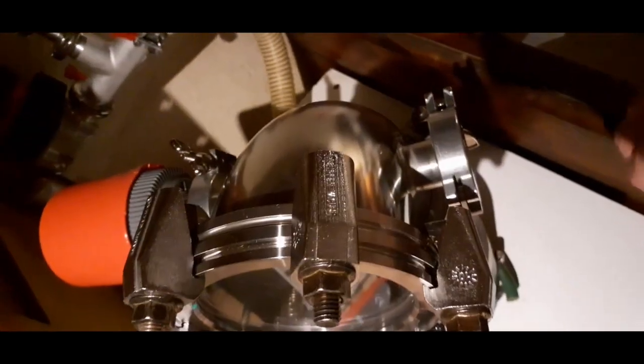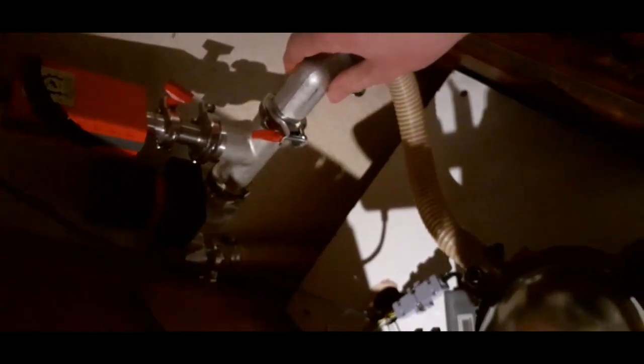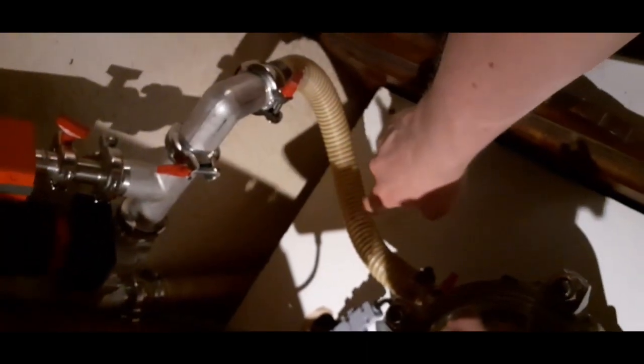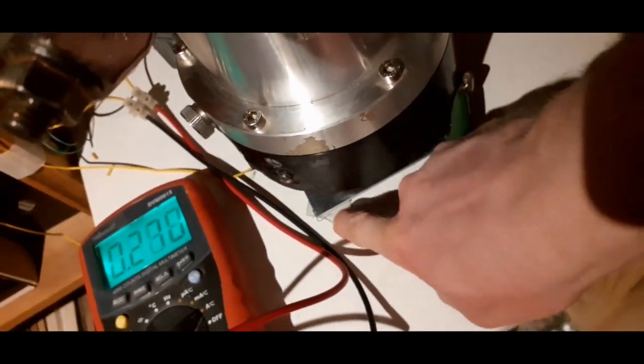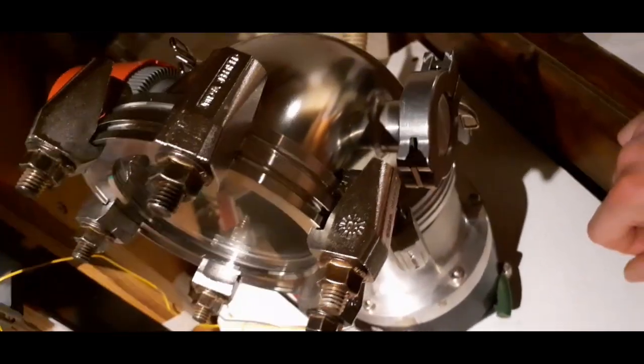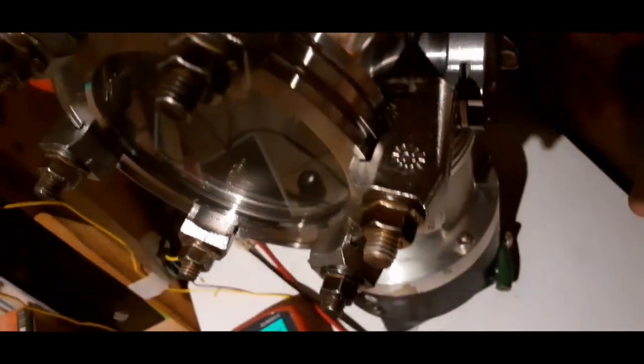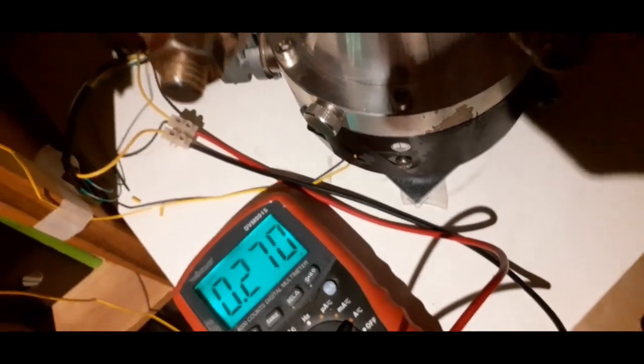I've tried to reduce that by decoupling the input manifold here, the foreline, with some flexible hose, so it doesn't sit and act as a tuning fork. And I've tried to put some gel tape underneath it to kind of decouple it. It helped a lot. Before it was so loud that it deafened out the foreline pump. But it still has a sound. I think that's just the normal operating sound. It doesn't change in pitch. And normally you have to be a bit worried when turbos make a sound. But of course, they're never silent. So I think this is pretty much just fine.